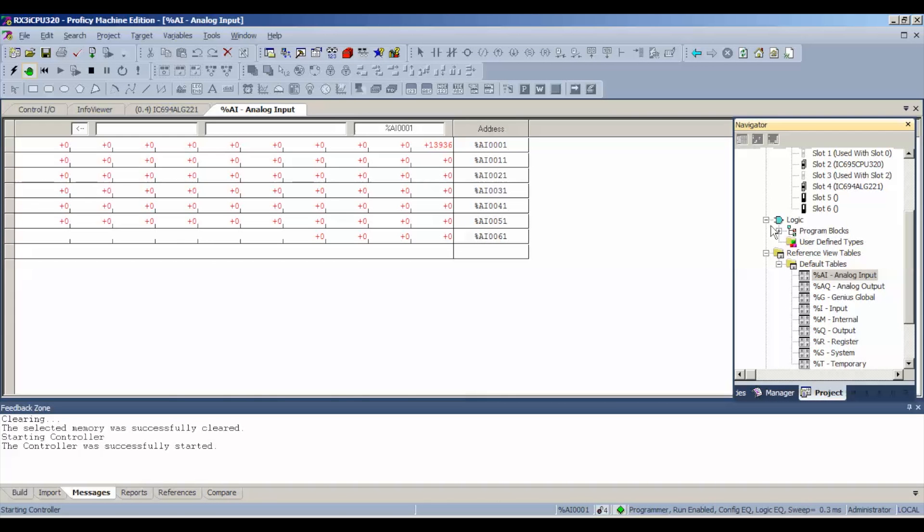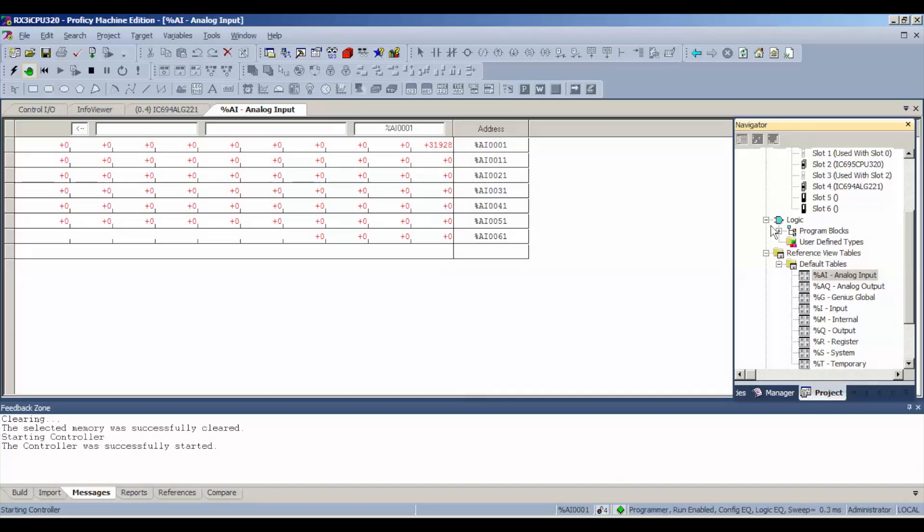Right now, I'm looking at the stability of the channel. Once I've stopped at this value that you see here, 11,712, it's not going up or down by large amounts. It's not fluctuating and fluttering. Then I dial it back up and I want to be able to get very close to 32,000, which is the value that would relate to 20 milliamps.